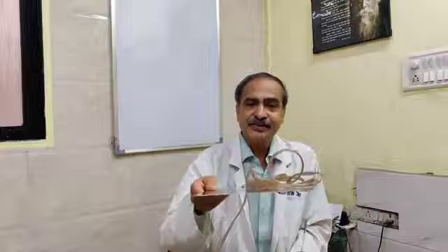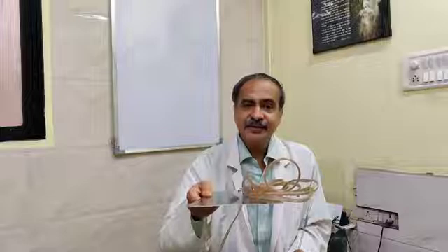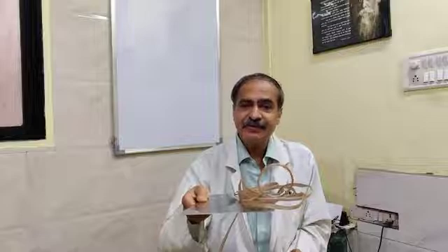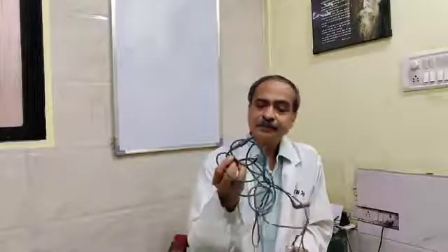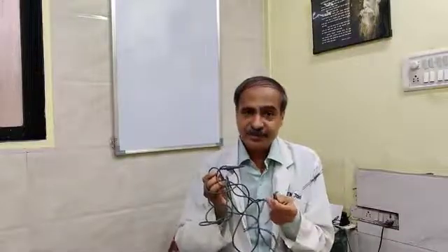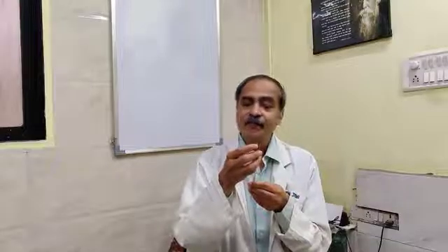One has to see whether it is attached to the patient, whether the contact of the passive electrode with the patient is intimate and broad, and whether the connection of the passive electrode to the cautery has been properly done. Then check whether the high frequency cord connection between the working element and the high frequency cord is proper, dry, and connected at the proper socket on the cautery. Also, see whether the loop is properly fitting with the working element and there is no insulation fault of the loop.